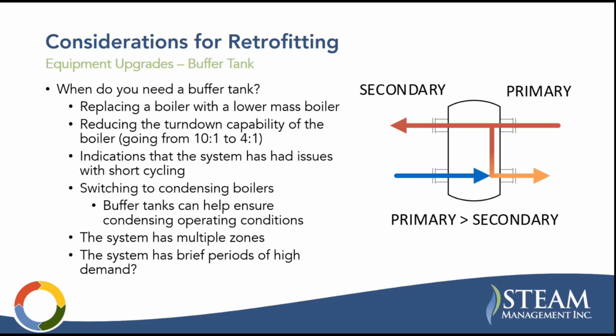We mentioned a buffer tank. So when do you need a buffer tank? Basically, a buffer tank adds volume to your system. So if you're replacing your existing boiler with a lower mass boiler, that's a good indication you need a buffer tank. If you're reducing the turn down capability of the boiler, and I'll show you in a sizing equation in a second why that matters, let's say you're going from a 10-to-1 turn down to a 4-to-1 turn down.